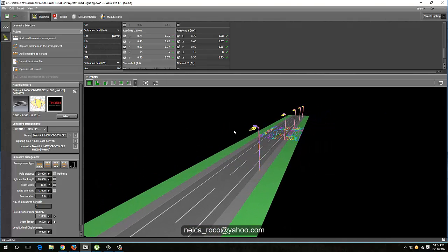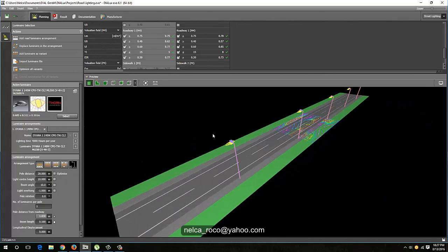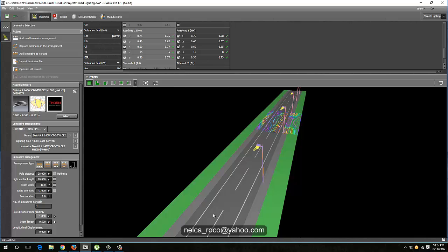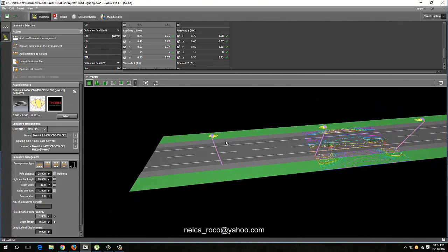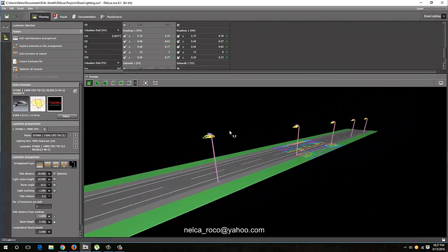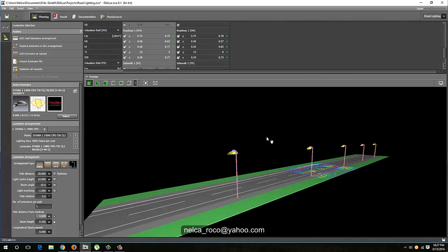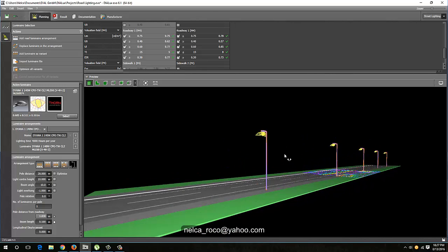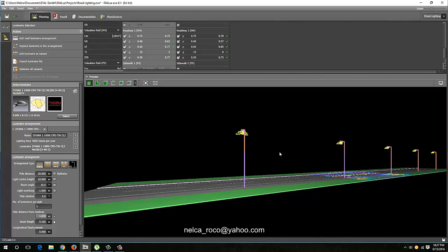So again, you can also play with the optics, because some luminaires have this kind of optic that can spread wide into the road. For now, I think on the contractor side, it's much better for them to have 36 pieces of poles and luminaires with an increased height of 10 meters, compared to the 10 meter spacing of poles, where you will have 100 pieces of luminaires and poles. With this new design, you only have 36 pieces of poles and 36 pieces of luminaires.